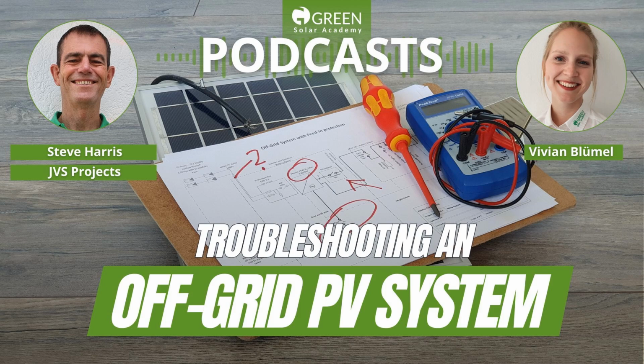One thing to remember is that a lead acid battery doesn't count a cycle in its internal chemical memory as a full charge and full discharge. Any time it starts to discharge and then recharges, even if it's only gone down 5 or 8%, that's a cycle in its chemical life.